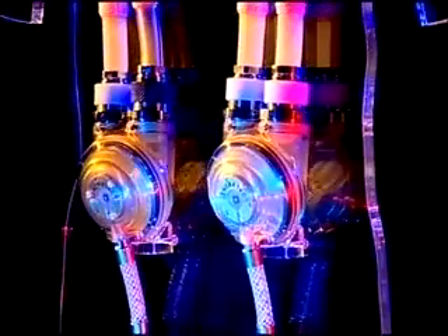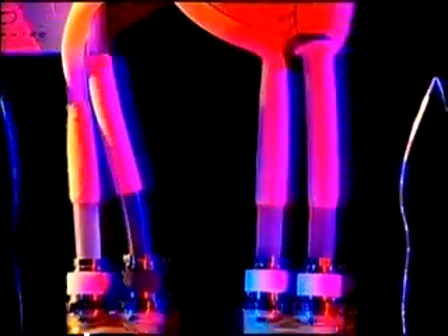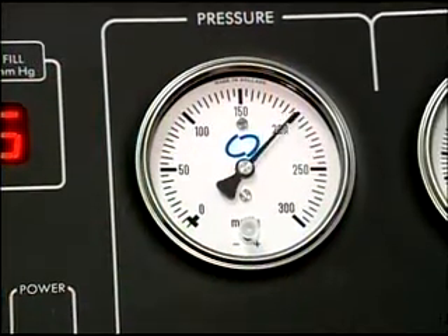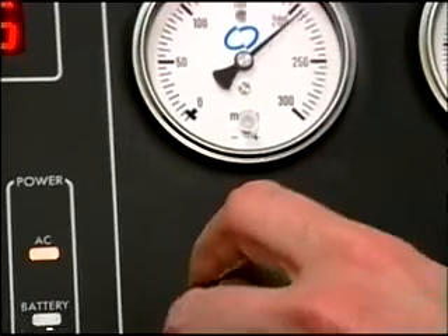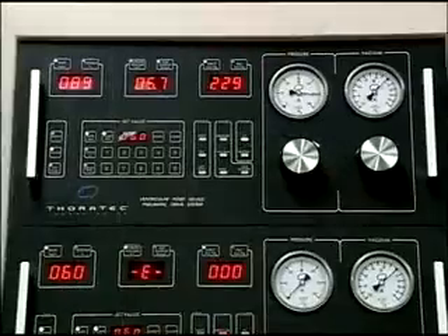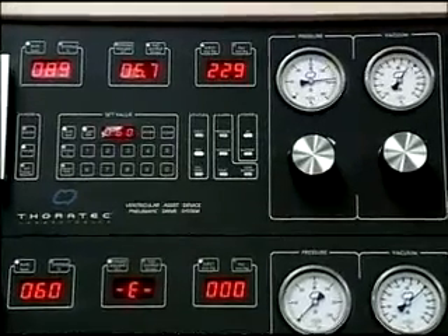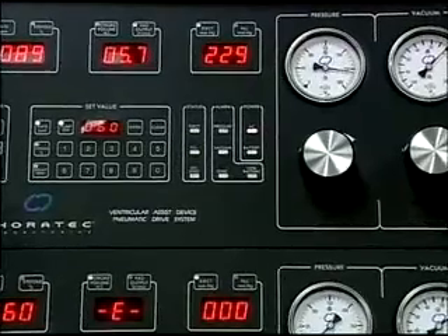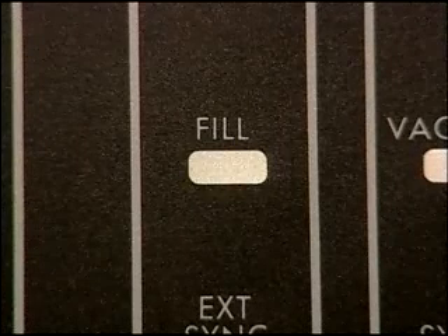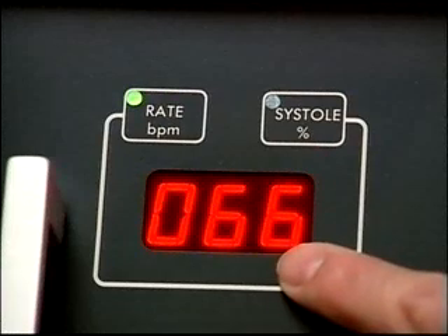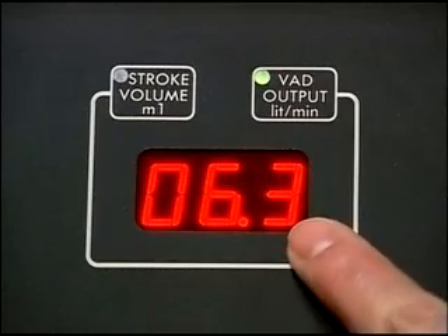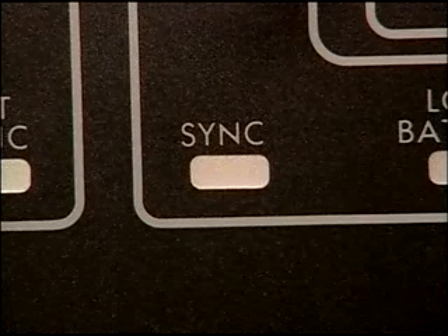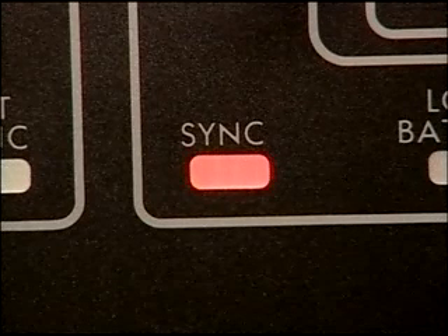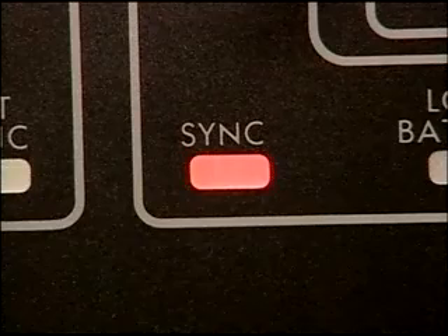When the pump is full, the drive module supplies air pressure during the ejection period to empty the blood sac into the patient's arterial system. The regulator control knob below the pressure gauge can be used to adjust the drive pressure. The console's fill indicator lights green when the VAD is completely full, triggering the beginning of the next ejection cycle. As the preload increases, the VAD will fill faster, decreasing each pump cycle. The pump rate and output will also increase, clearly indicated on the console. An alarm is triggered when the fill signal is lost in the volume mode. This is generally due to inadequate preload.